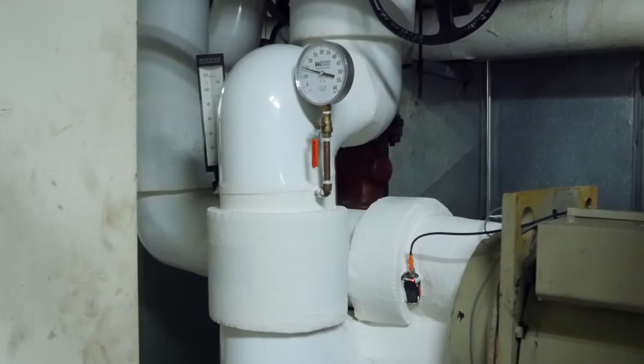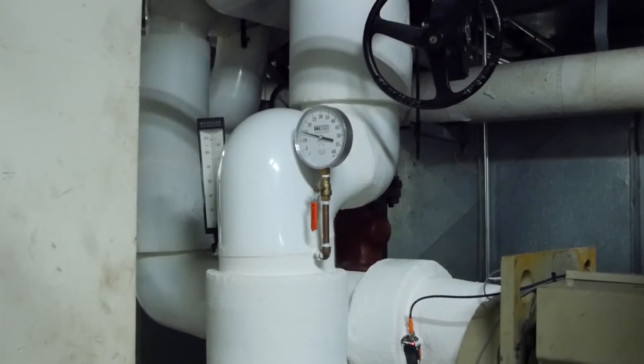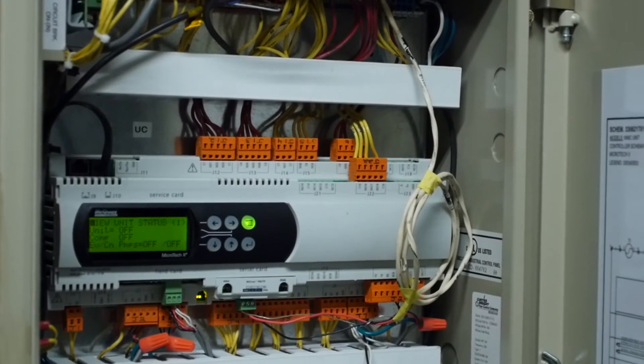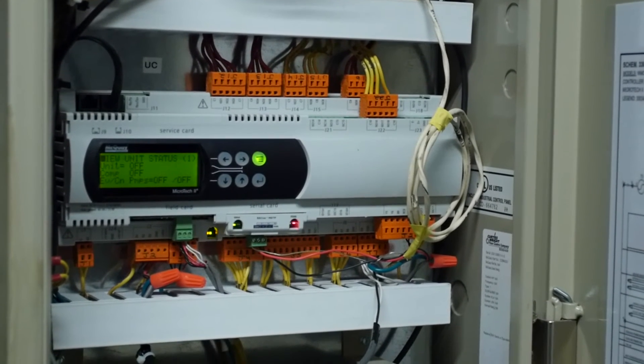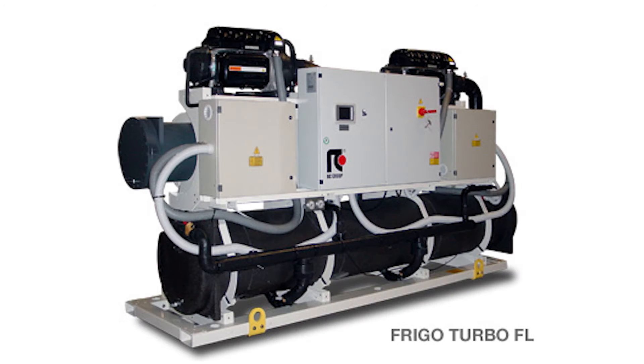We retrofitted the unit to obtain the longevity of the machine, and also to be able to remote start-stop and read all essential parameters without sending manpower up to that unit. The manpower issue was critical due to the fact that we had no control over condenser water, no control over chilled water. As of right now, we have full control.